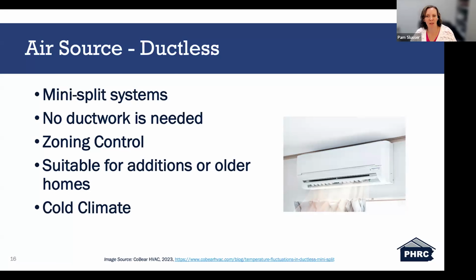This is hidden within the ceiling or wall with only grills or diffusers visible, often paired with short lengths of ductwork to distribute the air to multiple registers, similar to a ducted system, but it is a little bit different. Along with this, it offers zone controlling. So zone control, each indoor unit can provide independent temperature control for different rooms or zones. For example, you could have a mini split in your dining room and then a mini split in your living room.